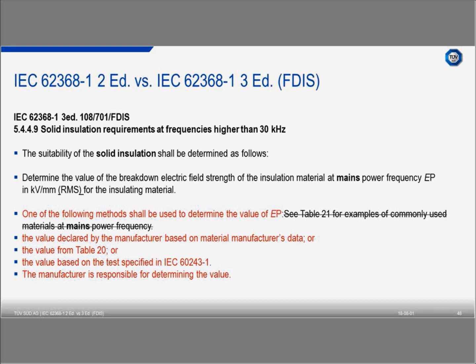There's an update for all the solid insulation requirements, so that in this case we can use a declaration by the manufacturer based on the material manufacturer's data, or we can use the tables, or we can use the results based on the test according to IEC 60243-1, and then we are more flexible. We know that the tables inside this standard are old, and maybe we have better materials now, so it gives a little bit more flexibility to use better materials with better results.